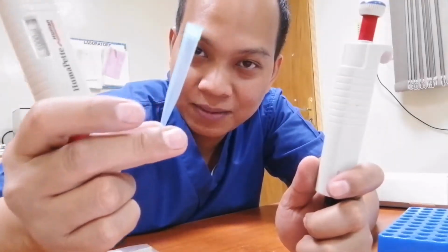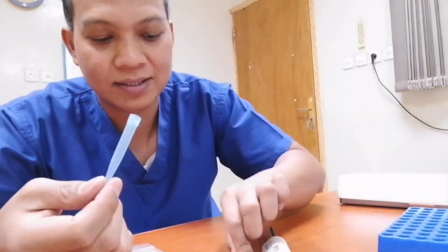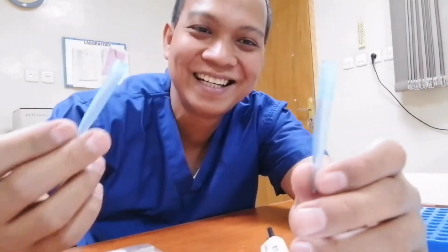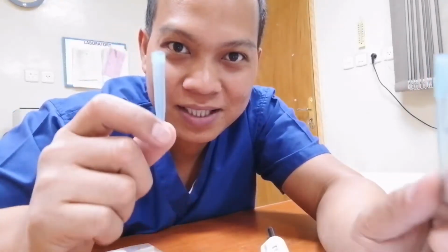So your pipette should be calibrated, okay? Even though you are using this kind of tips, these blue tips, especially when you are using this one. For us, we are using this one, not this one, because this one is expensive. But our pipette is calibrated not every 3 months, I do calibration every 1 month, for the best and secured volume for our pipette to use here in the laboratory. I don't like discrepancies in volume, especially in reagents, because it might give inaccurate results really.